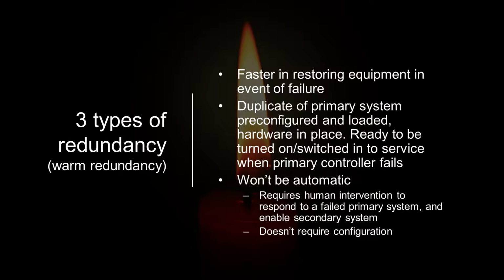For example, with a SCADA system, you might have a primary computer that runs your SCADA system, and in that same room a second computer always configured with the up-to-date configuration. If the primary computer were ever to fail, it's just a matter of turning on the new computer, perhaps moving some network cables, video cables, or peripherals, and then you're back up and running. This could be a potential cost-effective way to provide some level of redundancy depending on your application.